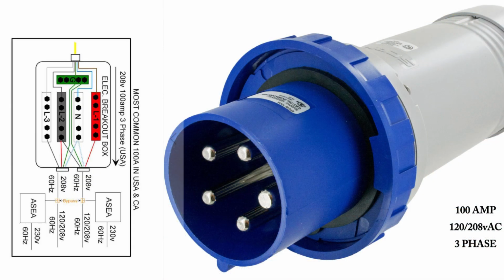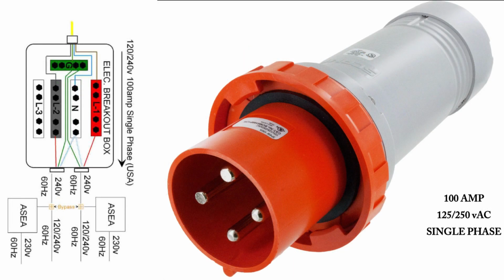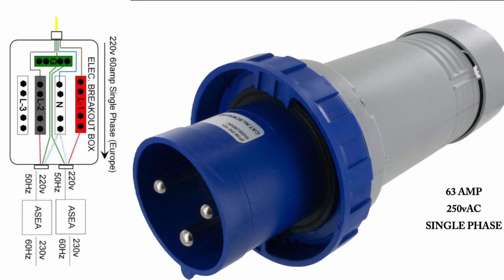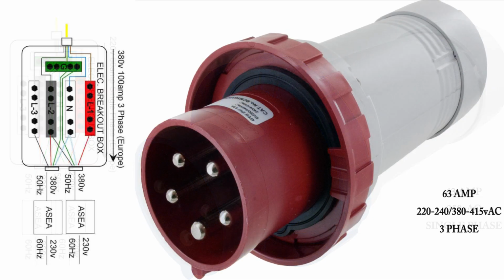In North America, we typically plug into a three-phase 100-amp, 120/208-volt AC outlet, or a single 100-amp, 125/250-volt outlet. Europe presents an even more varied challenge, but generally we can get away with either a 63-amp single-phase 250-volt or 63-amp three-phase 220/240 or 380/415-volt plug.